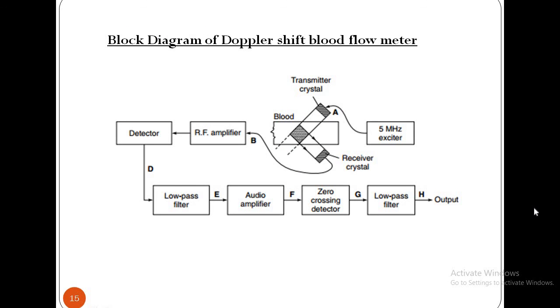Block diagram of the Doppler shift blood flow meter is shown in the figure. The piezoelectric crystal A is electrically excited to generate ultrasonic waves which enter the blood. Ultrasound scattered from the moving blood cells excites the receiver crystal. The electrical signal received at B consists of a large amplitude excitation frequency component which is directly coupled from the transmitter to the receiver plus a very small amplitude Doppler shifted component scattered from the blood vessel.